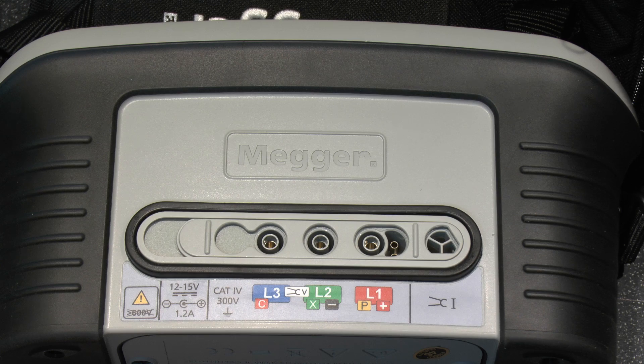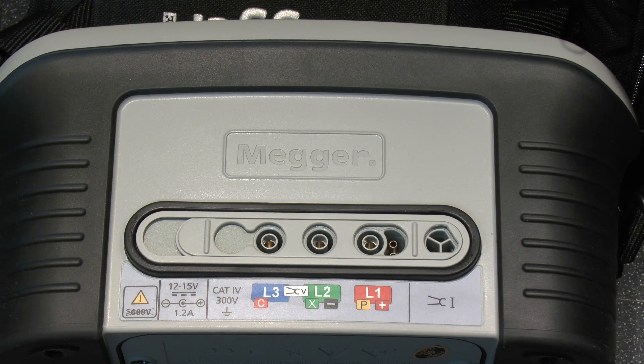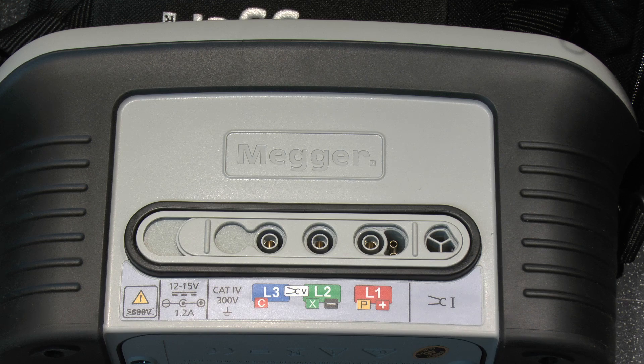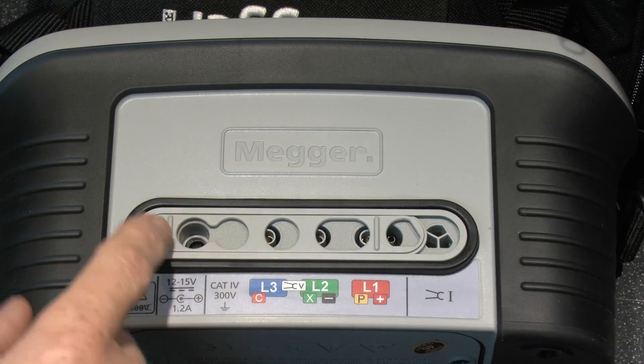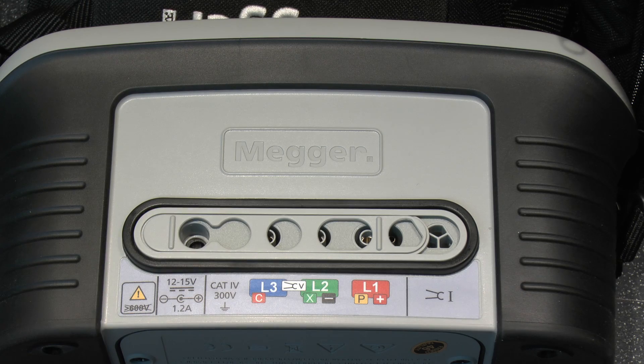On the front there are connections for the test leads — three of them, colour coded red, green and blue, matching the leads it comes with. There's also a port for a current clamp as an optional accessory. Sliding this cover to the charging position exposes the charging input — 12 to 15 volts, 1.2 amps — and the sliding mechanism means you can't have test leads plugged in while charging.